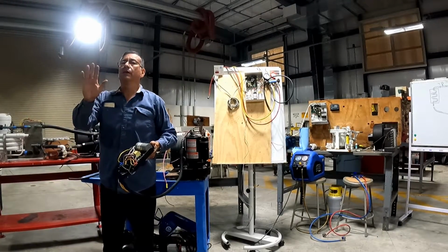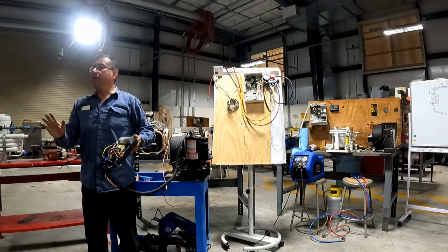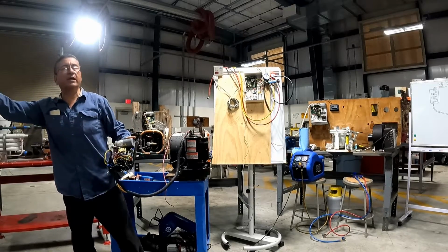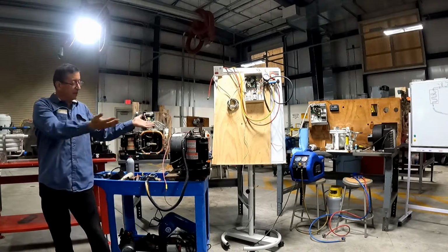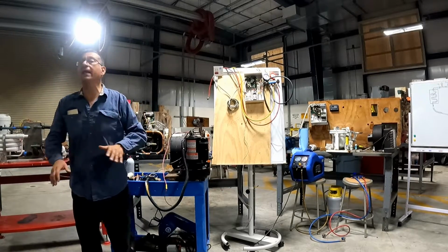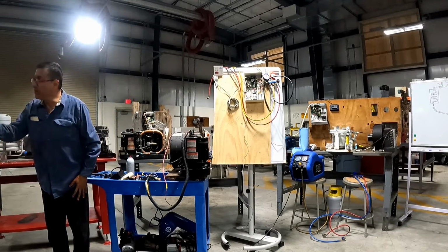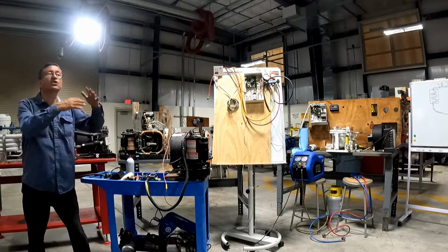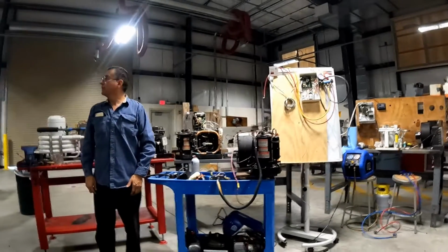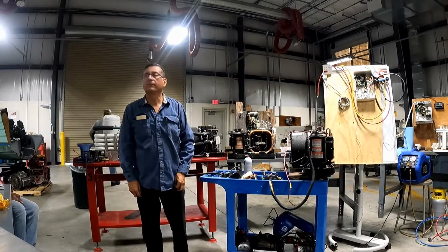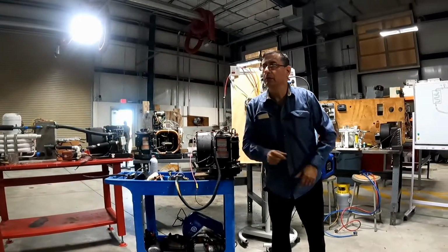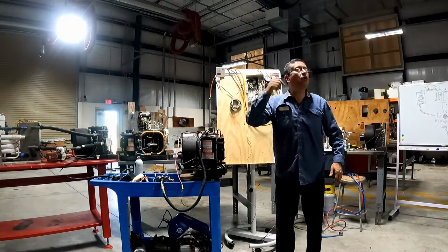Okay, other question. Mr. Lopez, everything is good. The triac is good, the thermostat is good, the power on the breaker is good, but the compressor ran an hour ago, stopped, and right now doesn't start again. The air conditioning unit was running and stopped suddenly, and now it doesn't start. What is the problem? High pressure switch? It's possible.